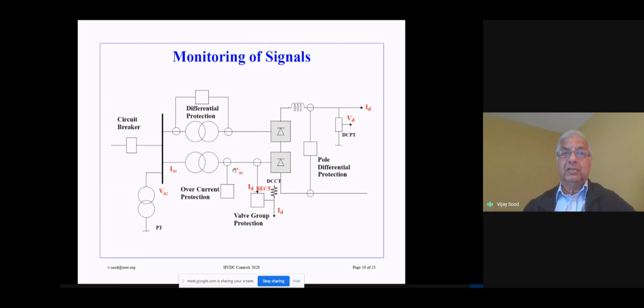This monitoring over here can also be utilized for overcurrent protection. So we monitor the currents coming in to the transformer, the currents going out of the transformer. These can be compared. So a differential protection scheme can be utilized. So here we can utilize this current and compare with this current to give us an overcurrent protection system. So various protection systems are indicated for the DC system. We monitor also the AC voltage. There's a PT over here, so that can monitor the AC voltage. You can monitor the AC current as well. So these can be linked into the circuit breaker for protection for any kind of fault on the DC system. So these are the various monitoring signals.